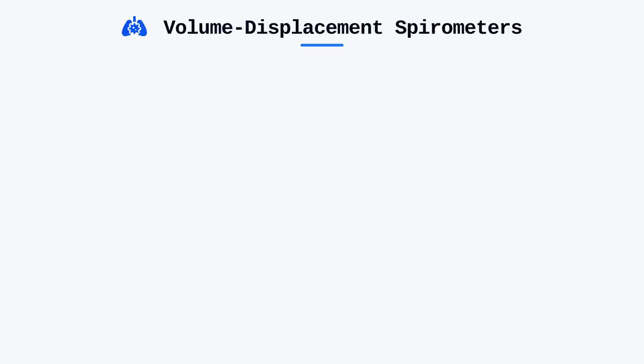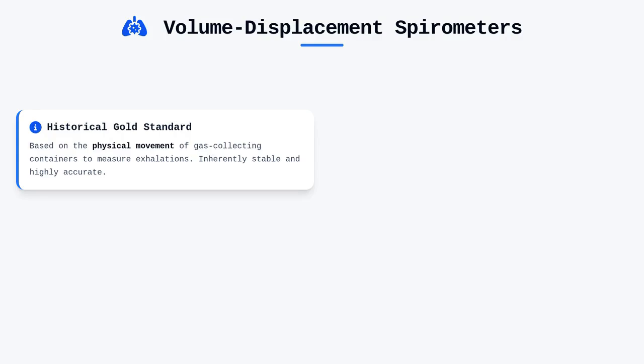Volume displacement spirometers were the historical gold standard, relying on the physical movement of a gas collecting container to measure exhalations. The water seal spirometer functions by utilizing an inverted bell floating in a water-filled chamber, where the patient's exhaled gas physically lifts the bell, providing a direct measurement of volume. While incredibly accurate due to its lack of mechanical friction, these units are largely absent from modern high-throughput laboratories due to their bulky nature and strict maintenance requirements.